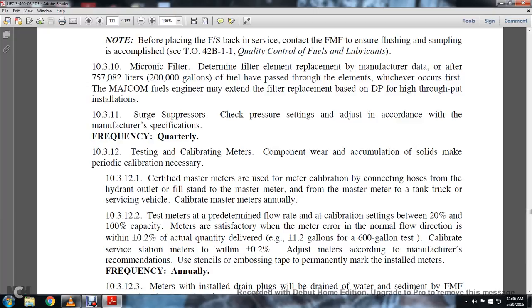Certified master meters are required or used to meter the calibration, with the connection hose from the hydrant outlet fill stand to the meter, and from the master meter to the tank truck or servicing vehicle. Calibrate master meters annually. Test the meters at predetermined flow rate calibration settings between 20% and 100% capacity. A satisfactory meter error is within plus or minus 0.2% of actual quantity, delivering 1.2 gallons for a 600 gallon test.